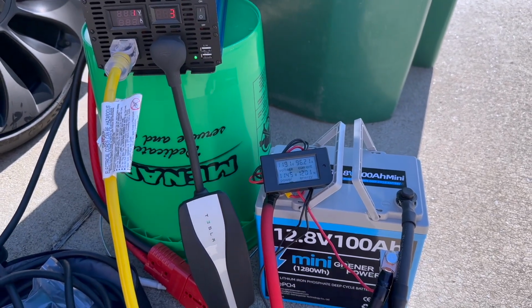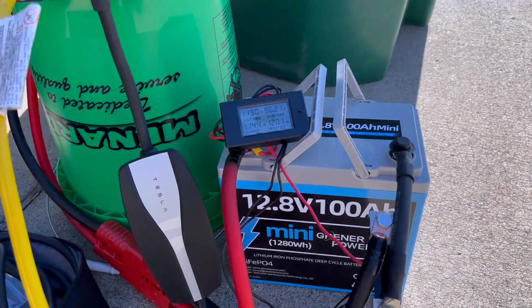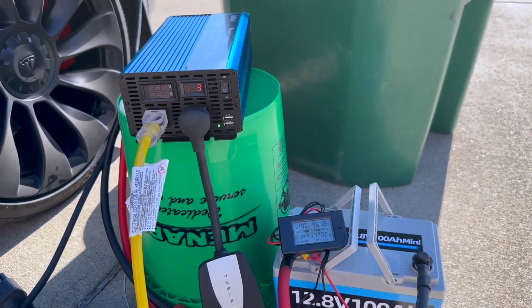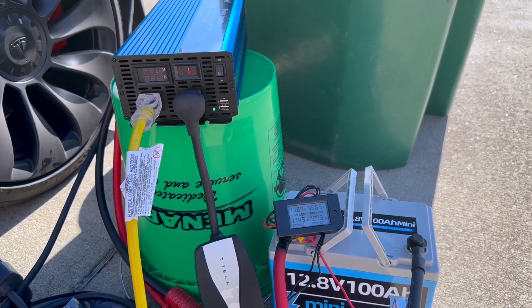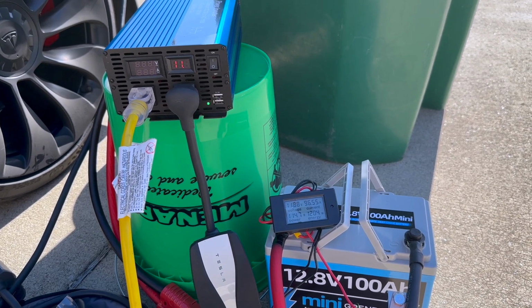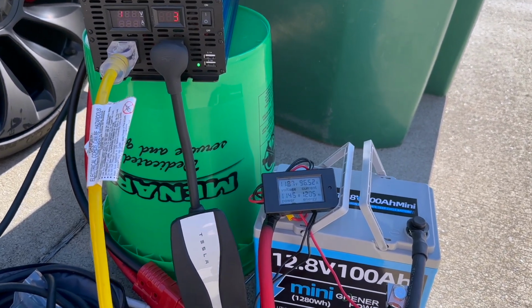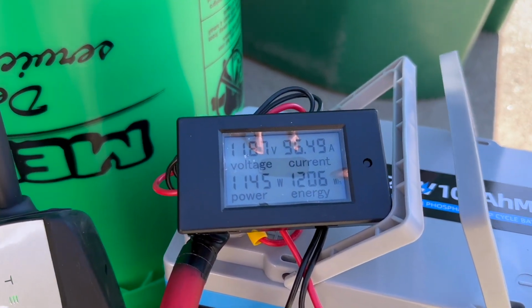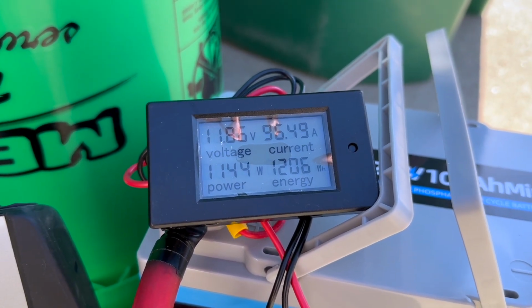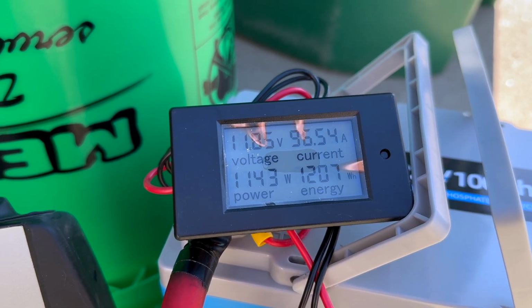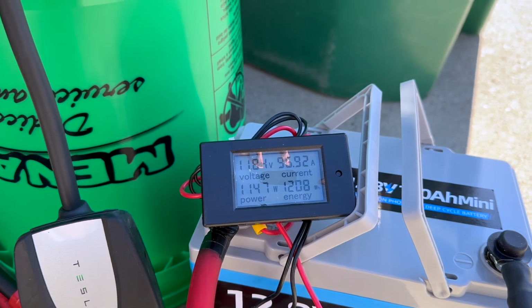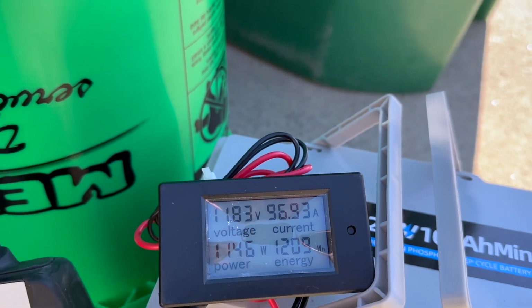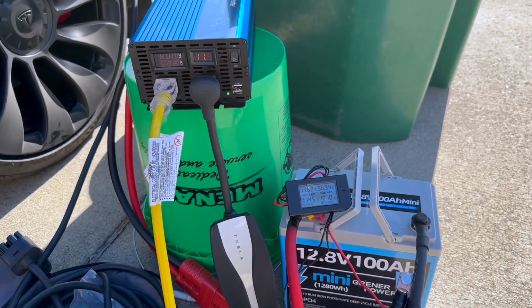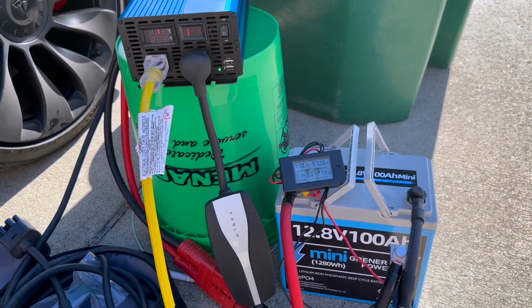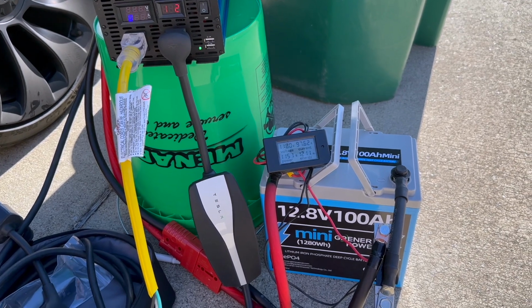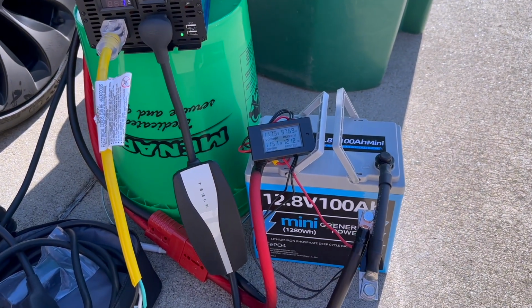So checking back in here, it might make it, it's rated at 1280, and I went to 14.2, so you could say there's a tenth of an amp or something left to pull out, but it's really starting to drop now. 1207 watts pulled out, we're at 11.85, and the current is 96, almost 97 amps. That's why I wanted to drop that down inside to 9, another good reason to keep below my 100 amp max output here.